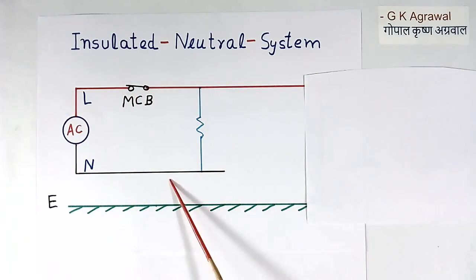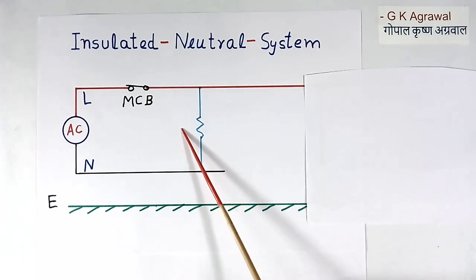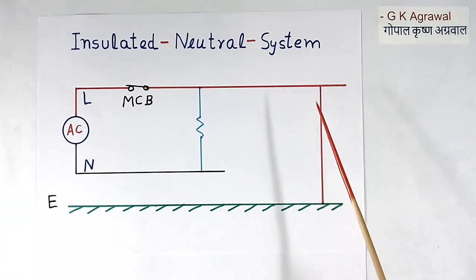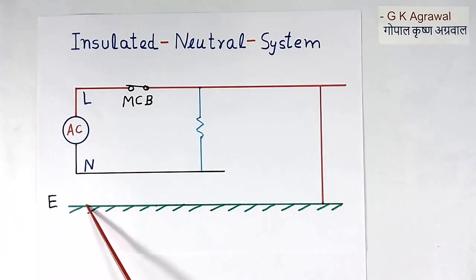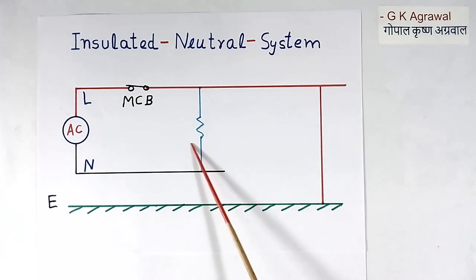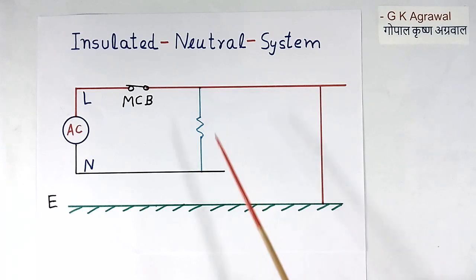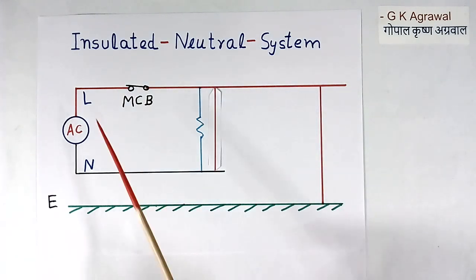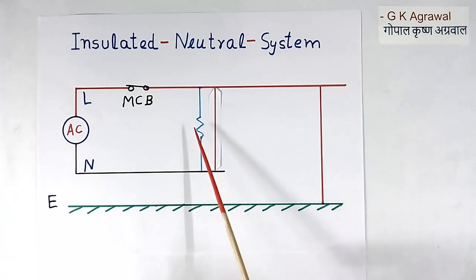The insulated neutral system is shown here again. There is no fault, so we are getting AC supply and the equipment is working. Now suppose there is a fault between line and earth. In this case also, as current cannot flow — it is open — AC supply will remain there. The MCB will not trip and this equipment will continue to work. Note: this is a fault between line and earth, not between line and neutral. If the fault is between line and neutral, then short circuit current will flow and the MCB will trip, and the equipment will not work.